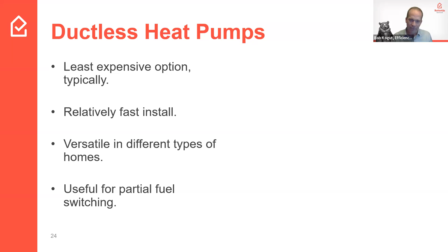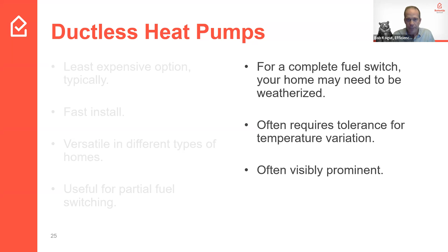Let's talk about fuel switching. If you want to completely heat your home with heat pumps, your house should be well weatherized, whether it's already in that state or you want to put some effort into doing that. That's probably one of the first things you should think about, even if you're in the market for a single mini split or ductless heat pump: first address the weatherization of your house. The better it's air sealed and insulated, the easier it is for any heating or cooling system, the less work it has to do, so you can use a smaller, cheaper system that works better down to colder outside temperatures. That's always something to think about.